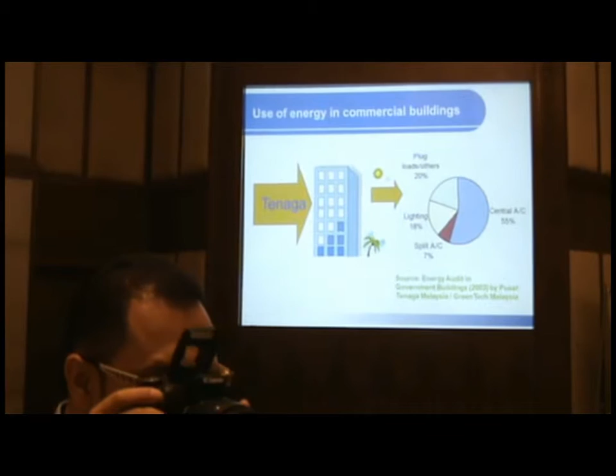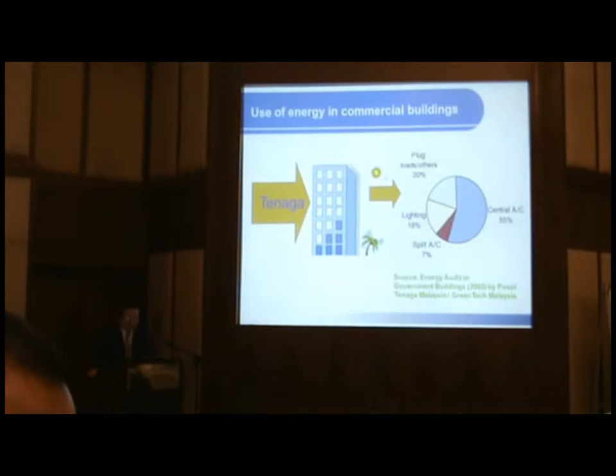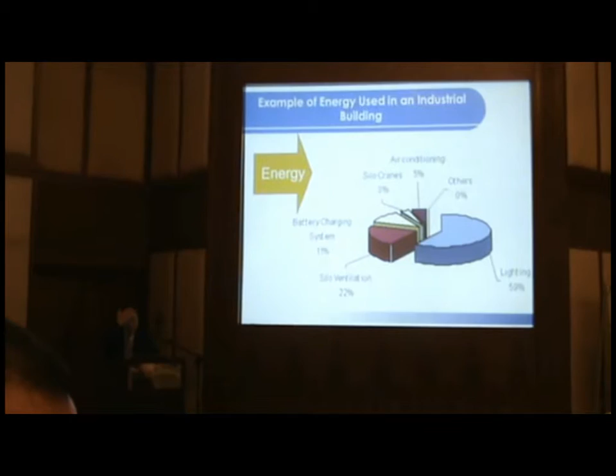One of the reasons is we believe the ICT equipment and ancillary, which is also the cooling system for the equipment, have increased proportions in the building. That's an area we actually need to look into, because nobody really looks into that. When it comes to ICT, I also designed that before, and there's always a missing link between IT professionals and the M&E or architect.